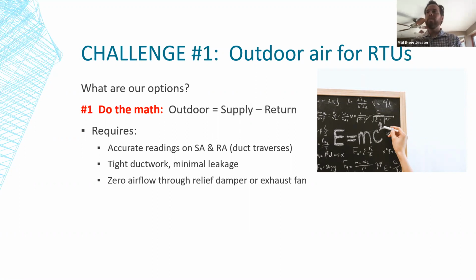And this is usually what will become an issue when you're trying to do this, is that return air. You know how on a rooftop unit, most of the time, if you've got a wild return, you've just got at most maybe a drop coming through the roof and an elbow for sound. That's not enough to get a good duct traverse. We're not going to be able to get an accurate reading on the return air then, which kind of throws this method out the window.